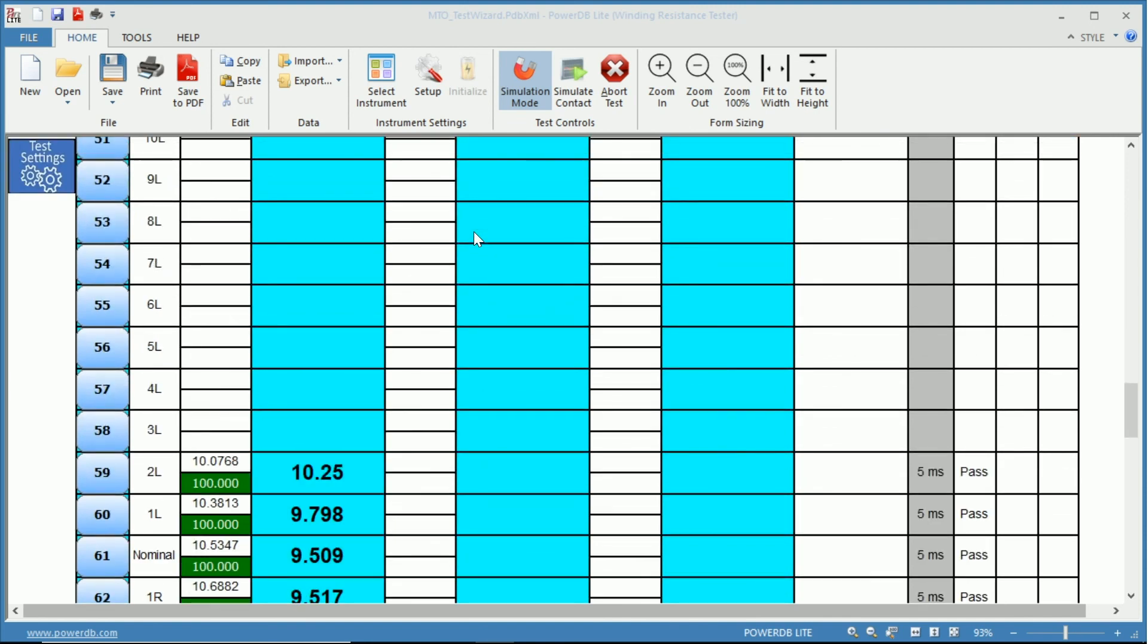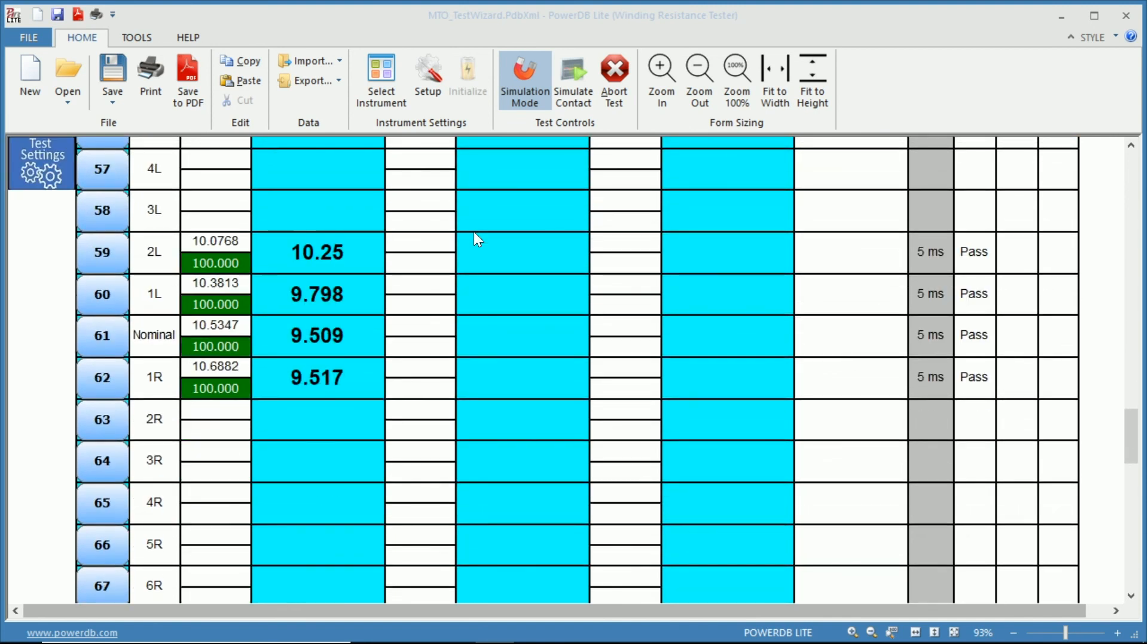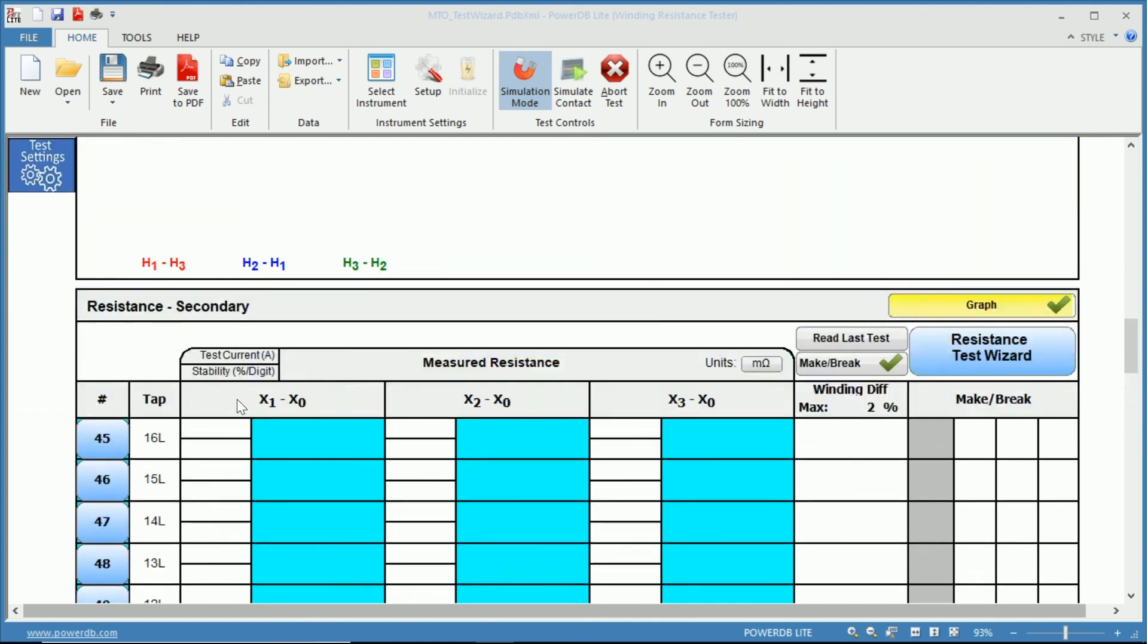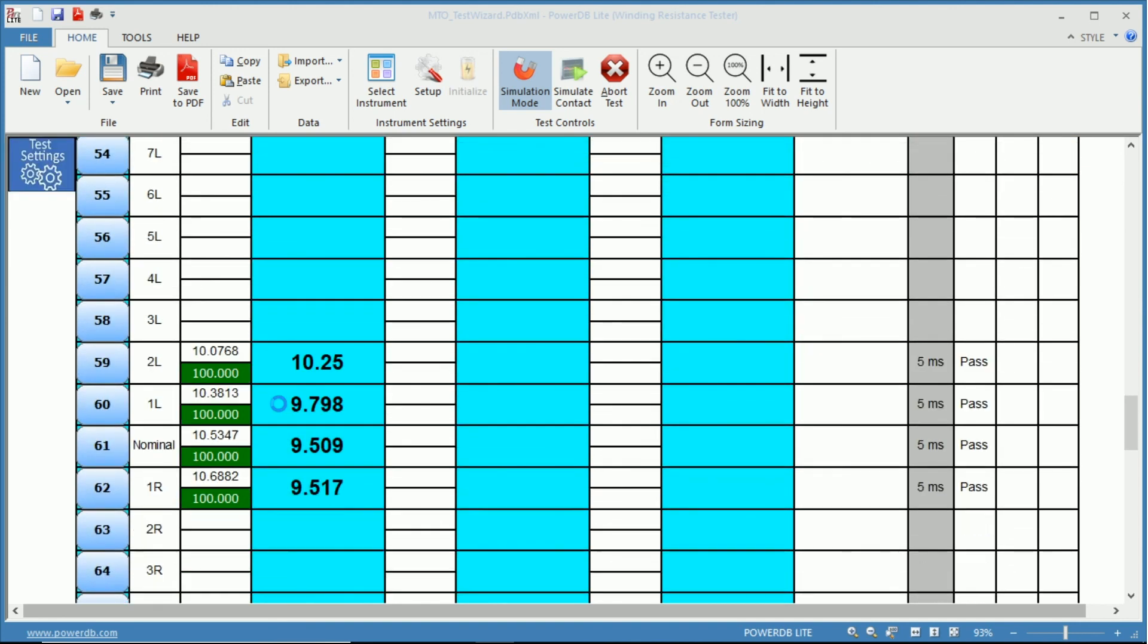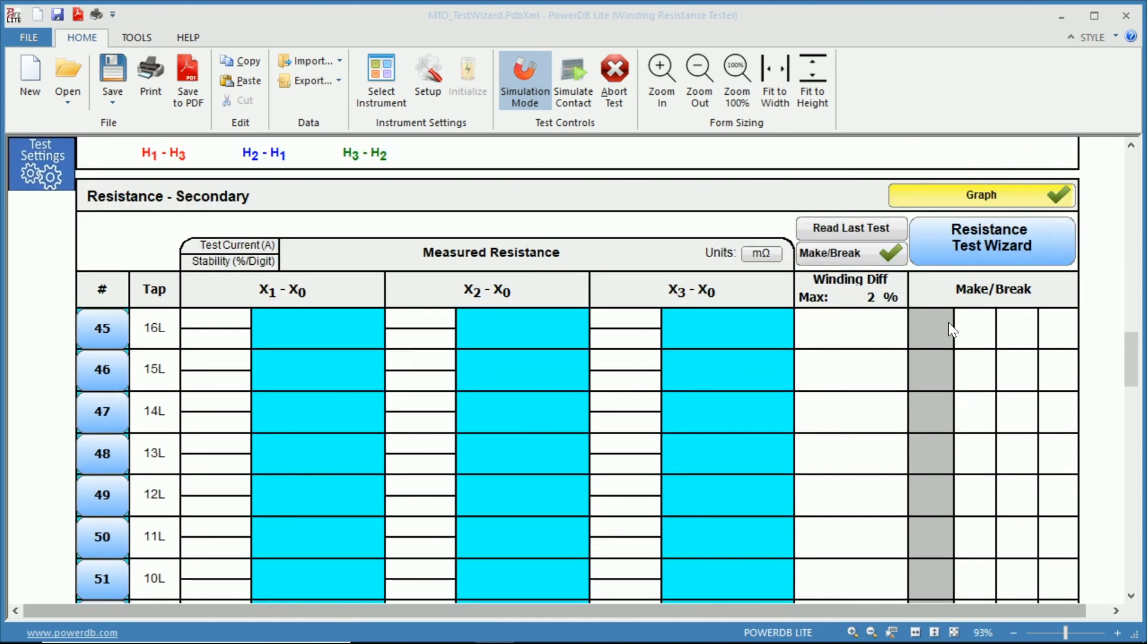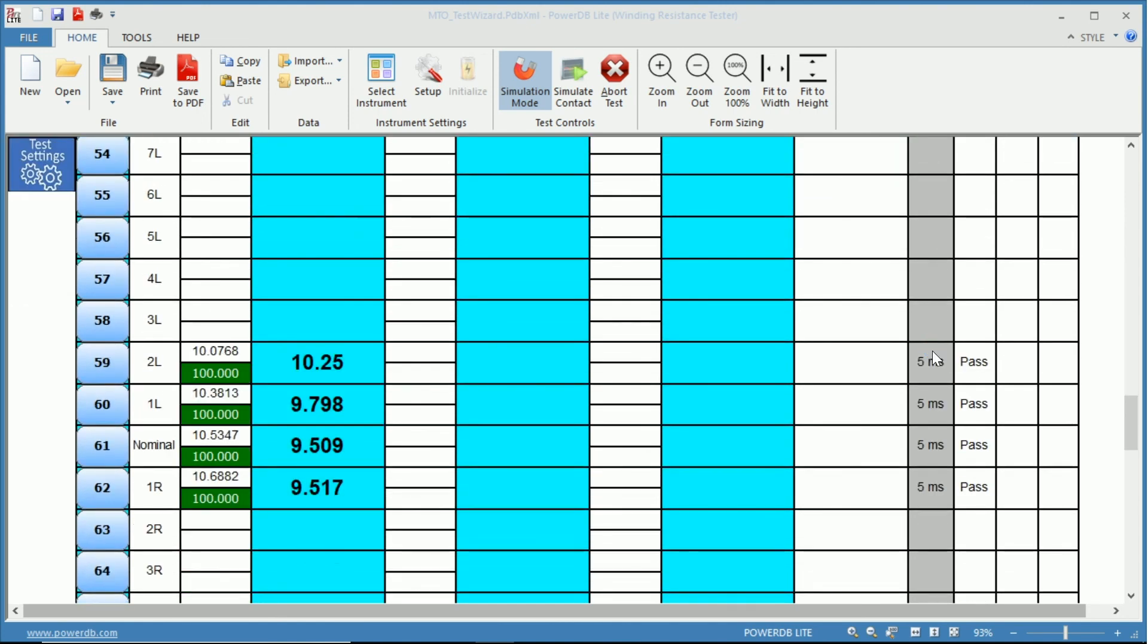Again, we are at the resistance for the primary side, so we need to scroll down to the secondary. And we tested taps two lower to one raise. We can see we have two lower, the test current, the stability, the actual resistance. All of these given at the top. So you have your tap, current, stability, and then the measured resistance in milliohms. We come to our make-before-break. We have our settings at five milliseconds. It passed each one.